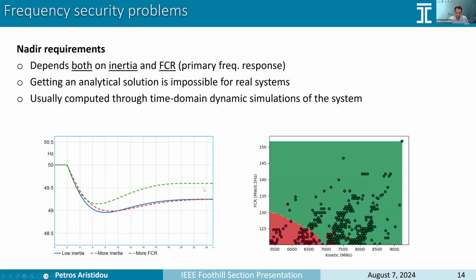On the right hand here, we see some scenarios. These come from the Cyprus system. On the x-axis, we see kinetic energy. So these are actual operating conditions taken from the SCADA system. On the x-axis, we see the kinetic energy that was connected to the system at that point. And on the y-axis, we can see the available frequency containment reserves. Then we simulated these scenarios where we tripped the worst case, let's say, generator, and we checked to see if the nadir goes below 49 hertz, which is the maximum allowed deviation.